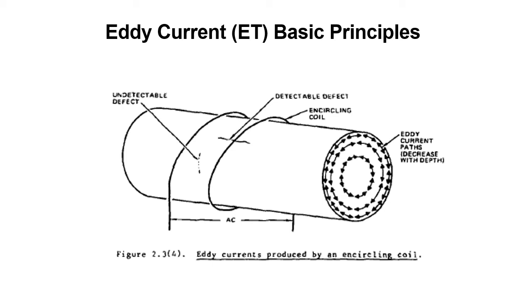Figure 2-3-4 shows an encircling coil installed around a rod. Here, Eddy Currents flow in the same direction as the current flow in the coil, i.e., around the circumference of the rod. Thus, the encircling coil is especially adapted to locating those discontinuities that are parallel to the length of the rod. The Eddy Current induced by the internal coil will be the same as the encircling coil, except the Eddy Current will be concentrated on the inner surface and not the outer surface.